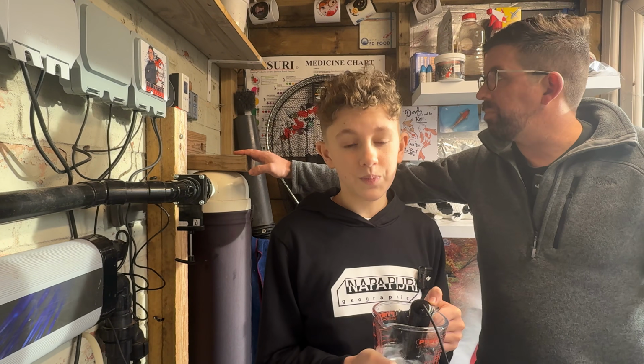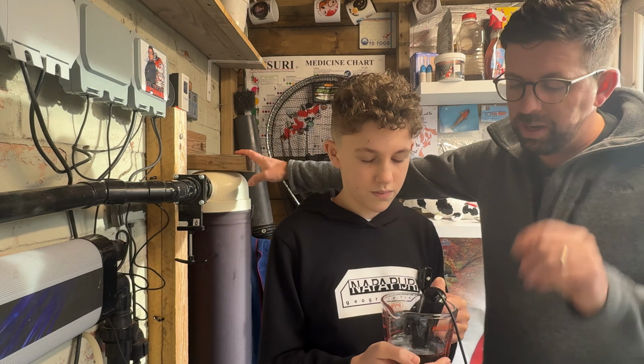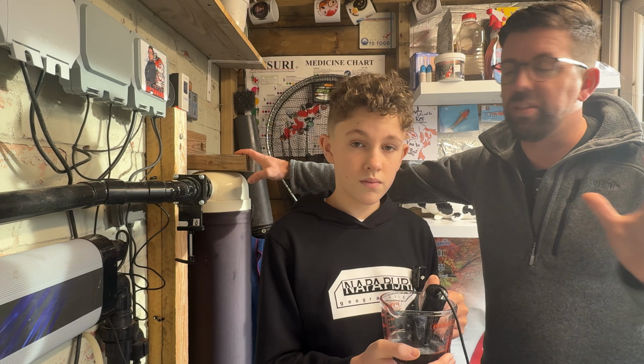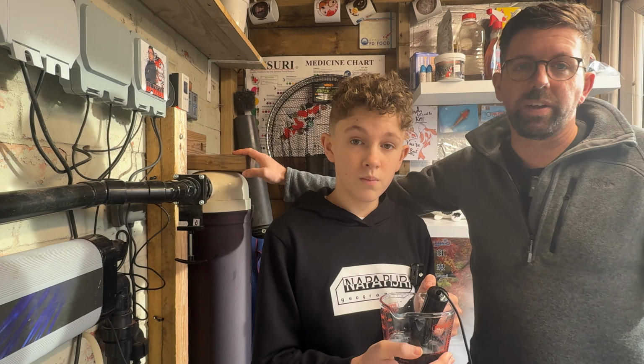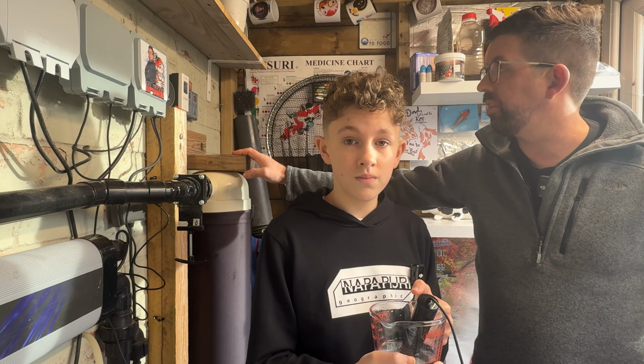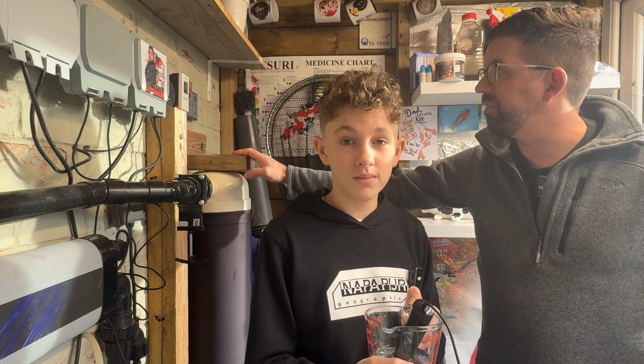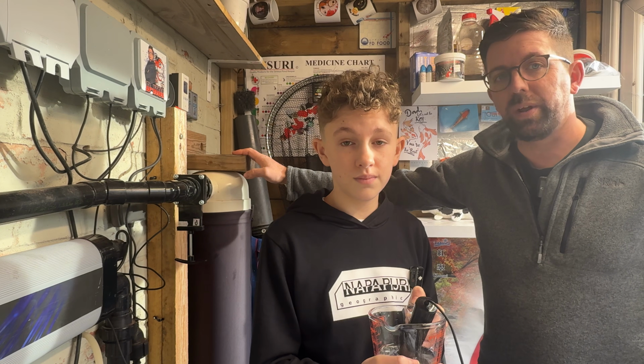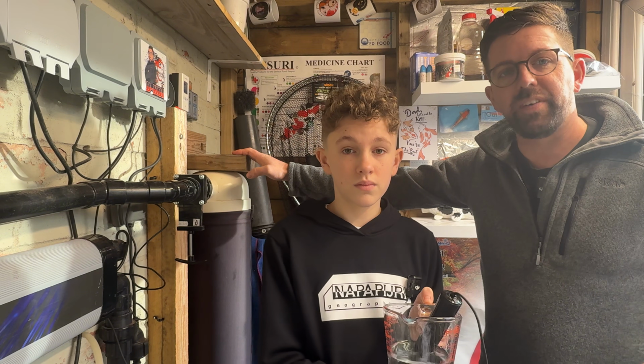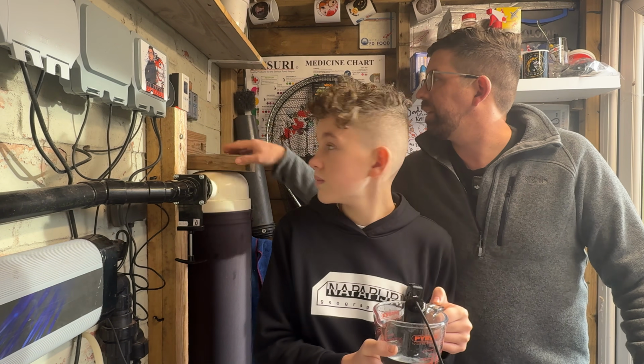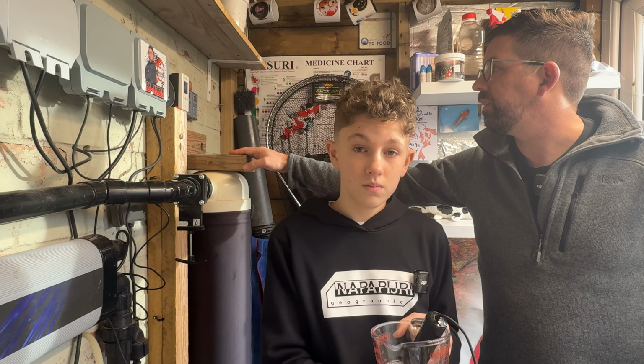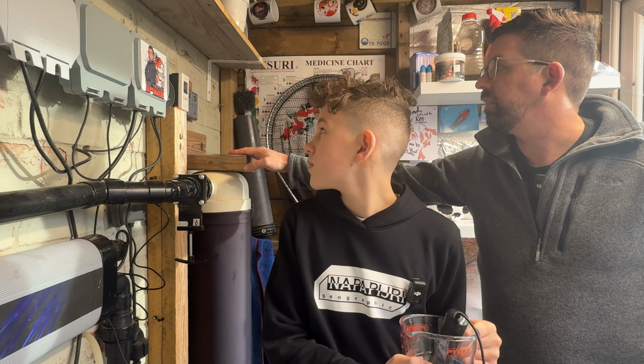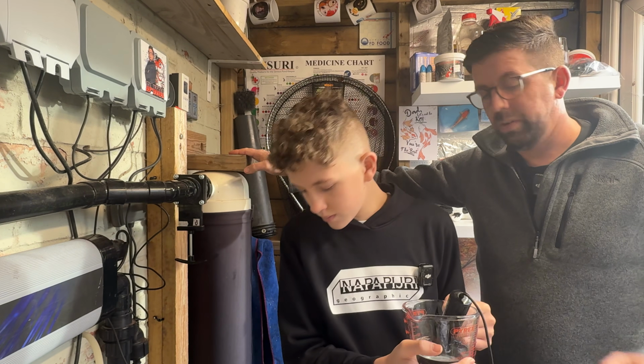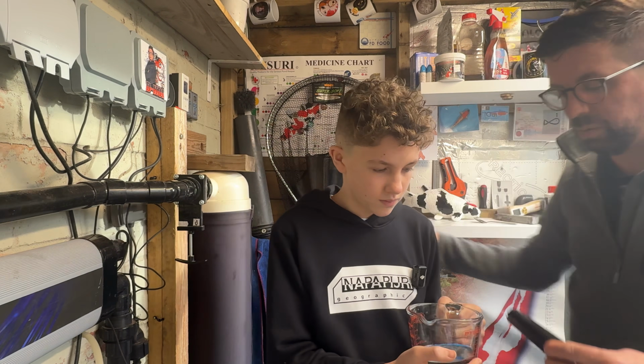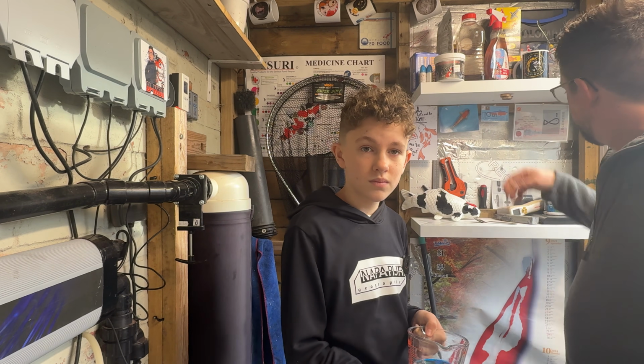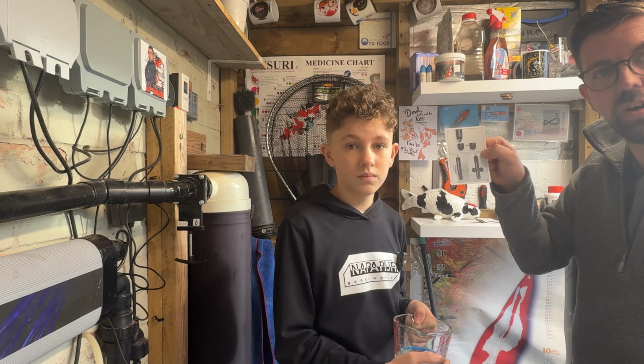Right guys, this is solution number 3, and one thing to take note of is when you're moving it from solution to solution, give it 30 seconds and the bottom part on the screen changes to the new solution, and it's got this at 9.50 and it needs to be at 9.18. So when you press calibrate, it sets it to that first figure. So I'll press calibrate again now on the screen. And there we go, we now have a green tick. So now this is ready to wash off in some clean purified water, and we'll stick it back in the filter and set the water height to what it says on the instructions.